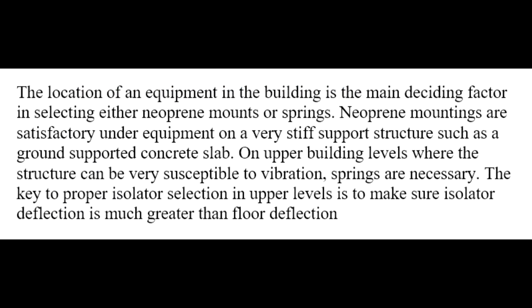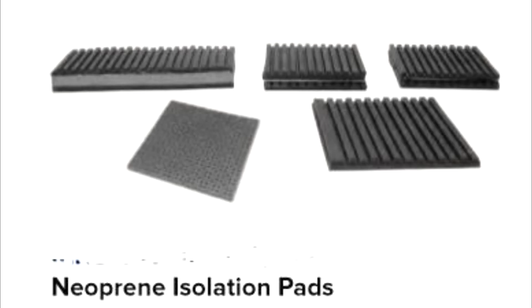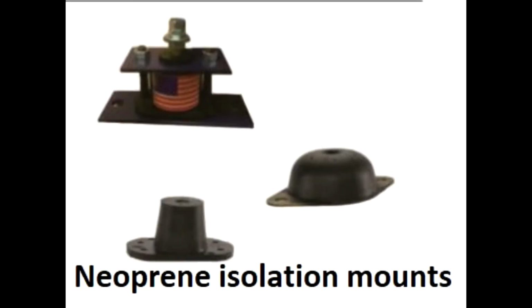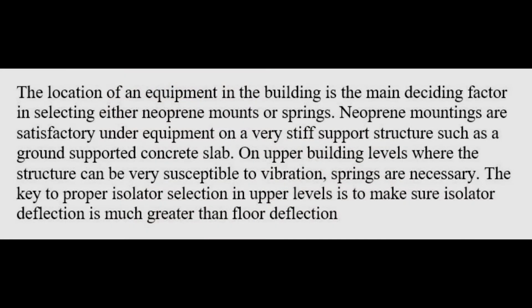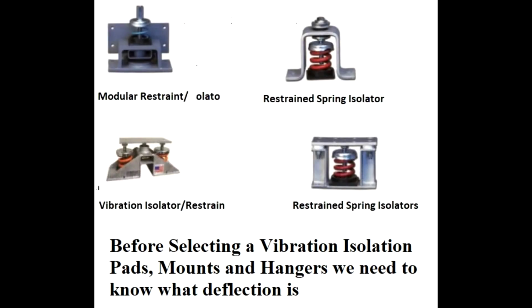We know that the location of equipment in the building is the main deciding factor in selecting either neoprene mount or spring. Neoprene mountings are satisfactory under equipment on a very stiff support structure such as a ground supported concrete slab. On upper building levels, where the structure can be very susceptible to vibration, springs are necessary. The key to proper isolator selection in upper levels is to make sure isolator deflection is much greater than floor deflection. Before selecting vibration isolation pads, mounts and hangers, we need to know what deflection is.